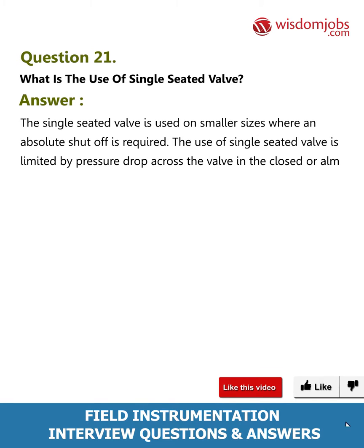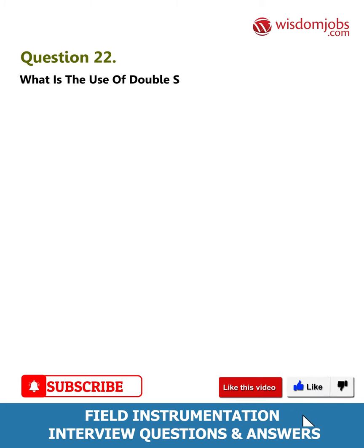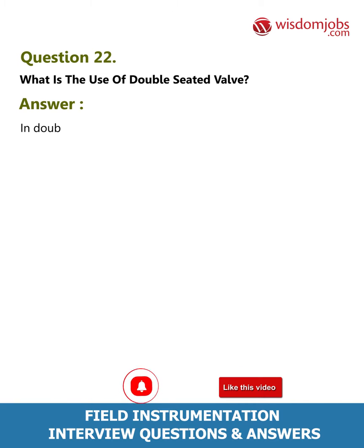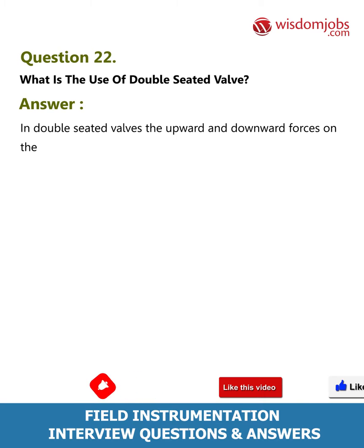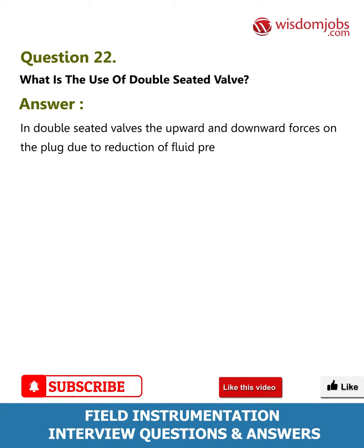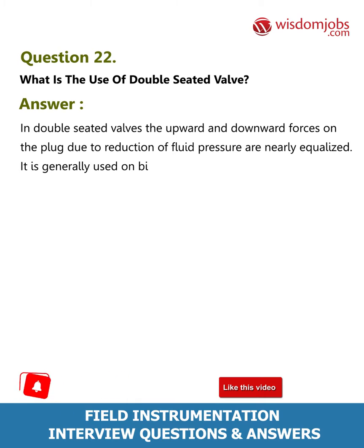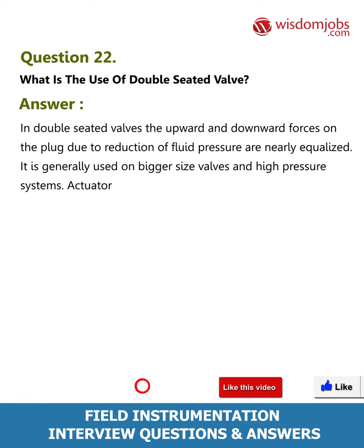Question 22: What is the use of a double seated valve? Answer: In double seated valves, the upward and downward forces on the plug due to the reduction of fluid pressure are nearly equalized. It is generally used on bigger size valves and high pressure systems, and the actuator forces required are less.